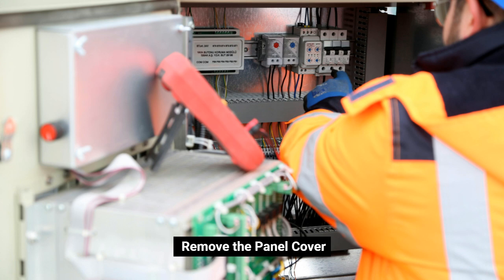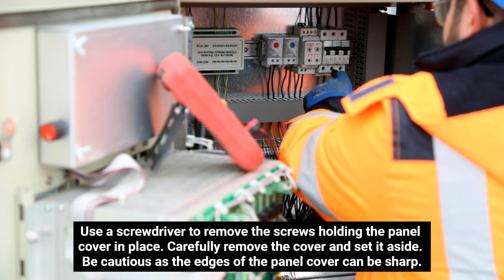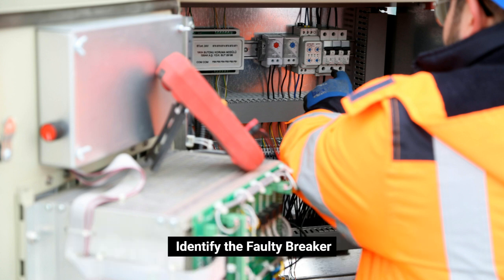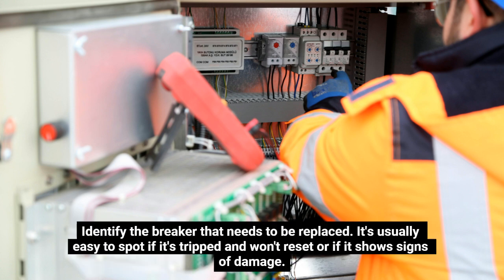Remove the panel cover. Use a screwdriver to remove the screws holding the panel cover in place. Carefully remove the cover and set it aside. Be cautious as the edges of the panel cover can be sharp. Identify the faulty breaker. Identify the breaker that needs to be replaced. It's usually easy to spot if it's tripped and won't reset or if it shows signs of damage.